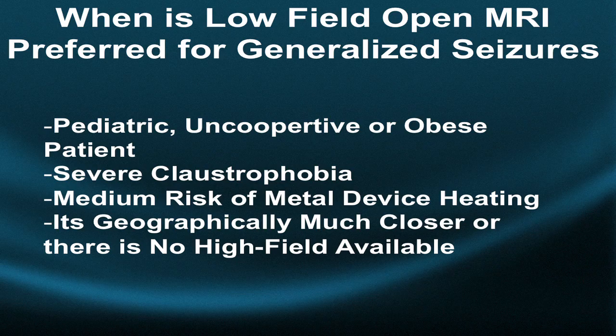Low field open MRI is preferred for young people who may be overweight or uncooperative, where you can stand next to them and soothe them through the opening. It's also preferred for patients with severe claustrophobia, and where there is moderate risk of a metal device in the patient — low field produces a lower risk of temperature elevation in such a device than a high field MRI system. Where high field is unavailable, low field MRI can do an excellent job in the brain in expert hands.